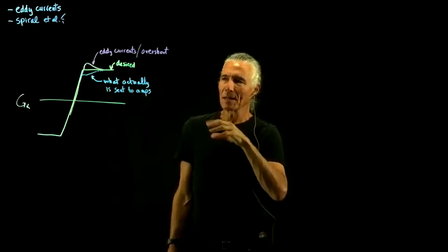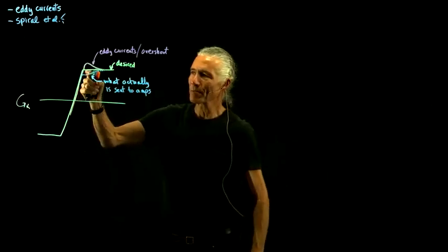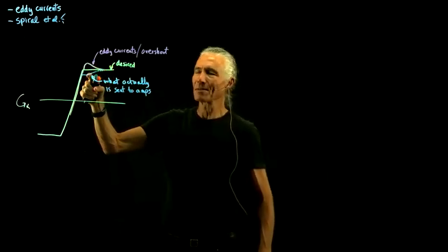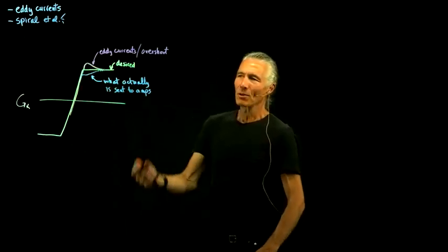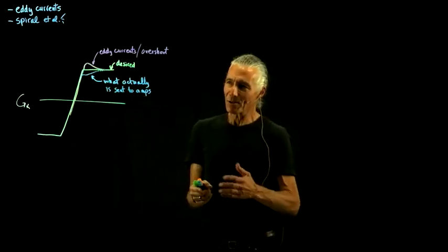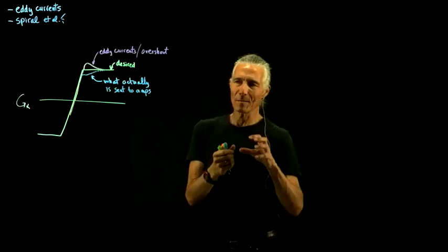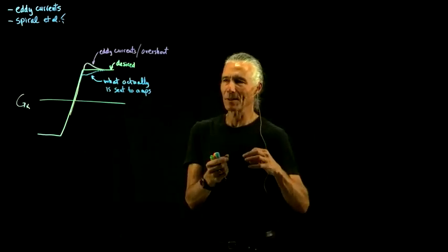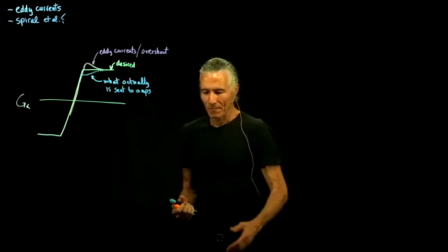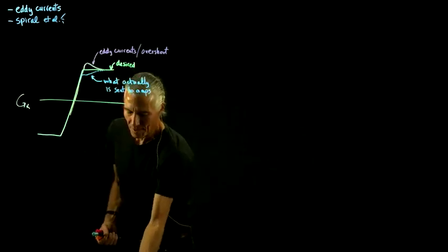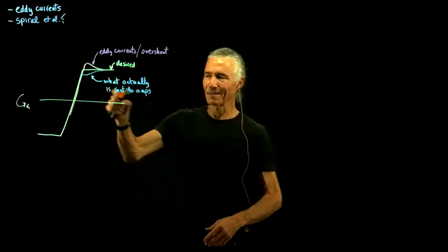So one thing you could do is try to do eddy current compensation and fix up the gradients. But the other thing you could do is, okay, we told you to do this and you didn't do that, but what did you do? You could just measure what the magnetic field was and then feed that back into the reconstruction. So there's multiple ways to fix this problem.